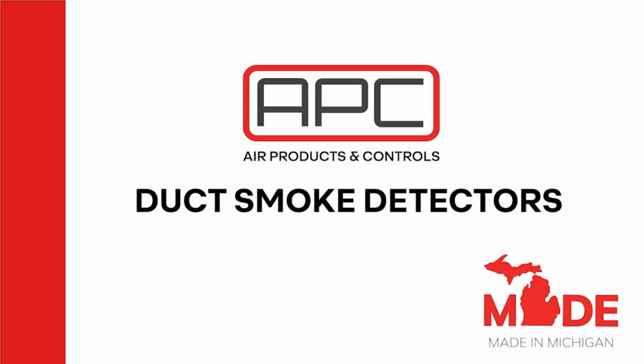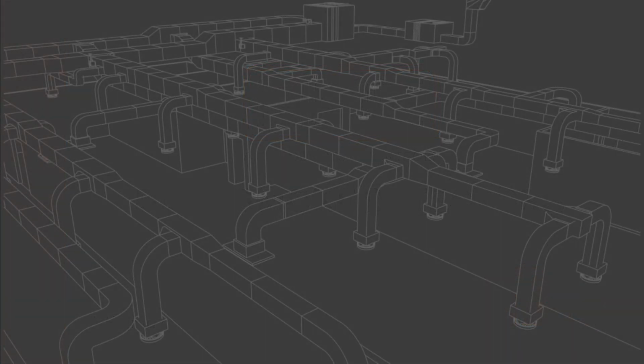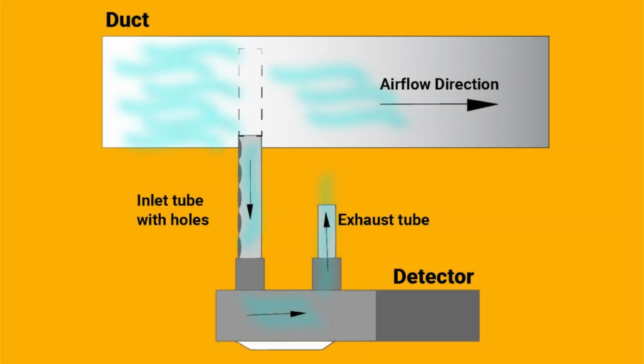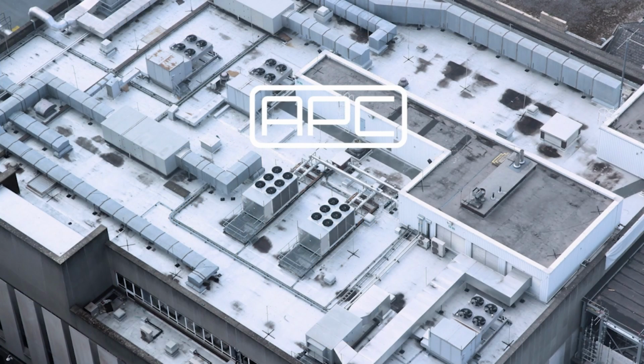Air Products and Controls Duct Smoke Detector Training. The duct smoke detector samples air moving through an HVAC duct. When the smoke threshold is exceeded, the duct smoke detector may be used to shut down the air handling units, close and open smoke dampers, activate exhaust systems, and activate a fire alarm signal, depending on what functions are required. The main purpose of a duct smoke detector is to reduce the spread of smoke, preventing injury and death. On a lesser scale, it also prevents damage from the recirculated smoke.